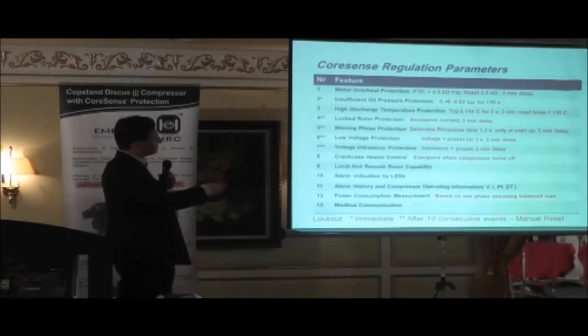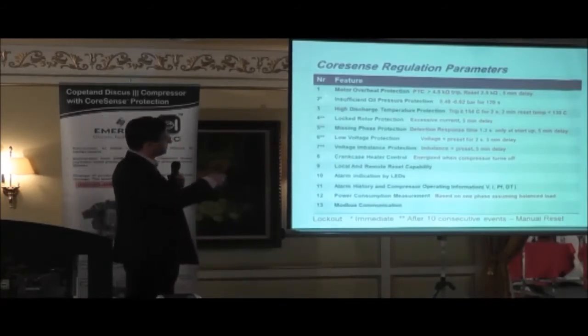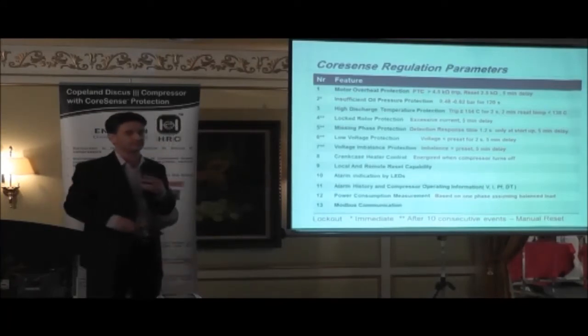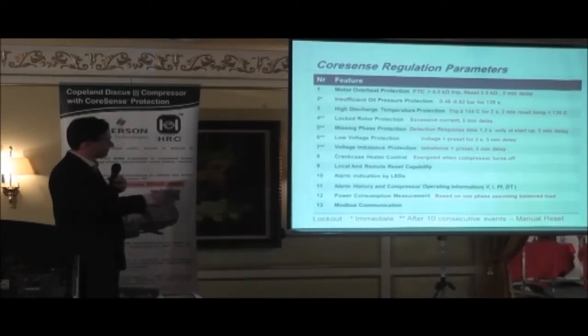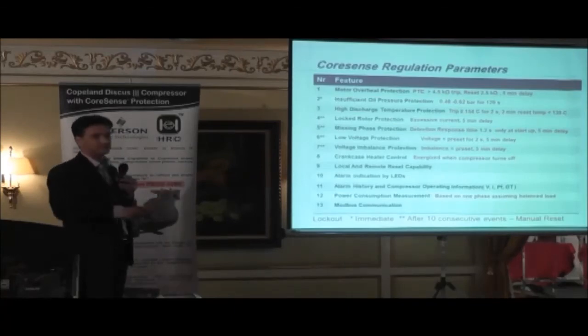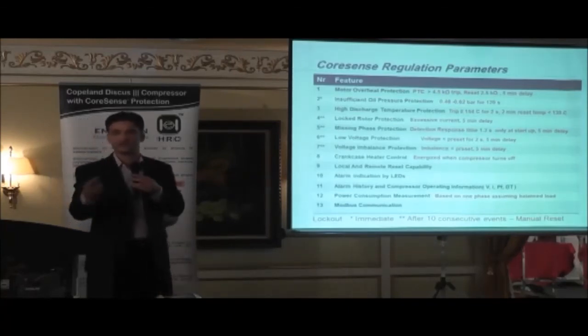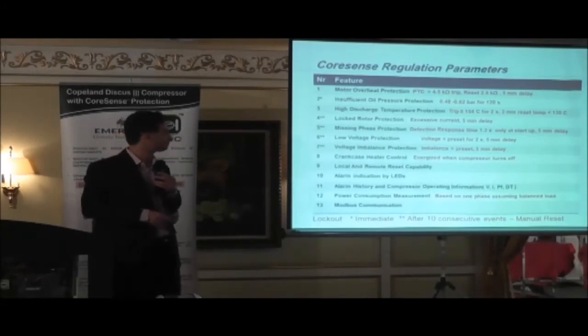And that's the same type of feature that we have on the oil pressure protection. If your oil pressure trips, it's a manual reset. Okay. So these are auto for the first 9 times. On the 10th attempt, it will go to manual lockout, and then you have to go and reset the compressor.